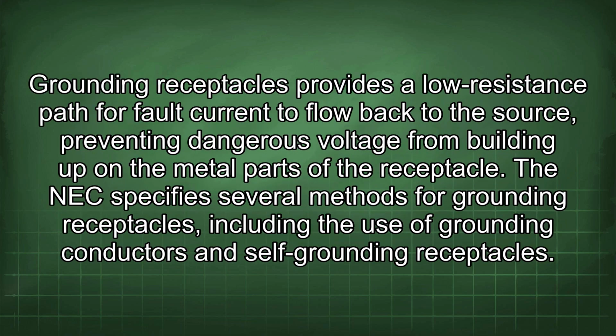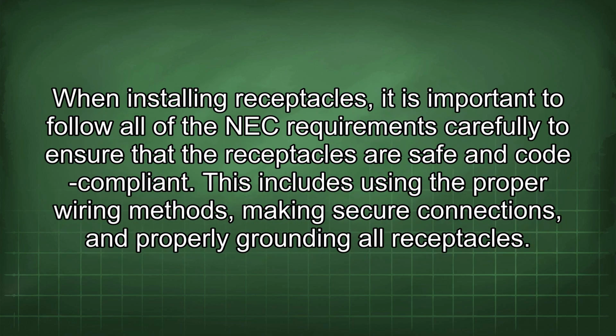One of the key requirements for receptacles is that they must be properly grounded. Grounding receptacles provides a low resistance path for fault current to flow back to the source, preventing dangerous voltage from building up on the metal parts of the receptacle. The NEC specifies several methods for grounding receptacles, including the use of grounding conductors and self-grounding receptacles. When installing receptacles, it is important to follow all of the NEC requirements carefully to ensure that the receptacles are safe and code compliant. This includes using the proper wiring method, making secure connections, and properly grounding all receptacles.